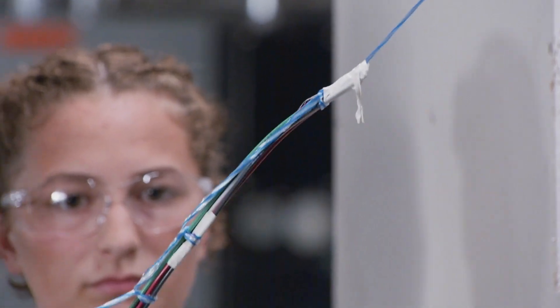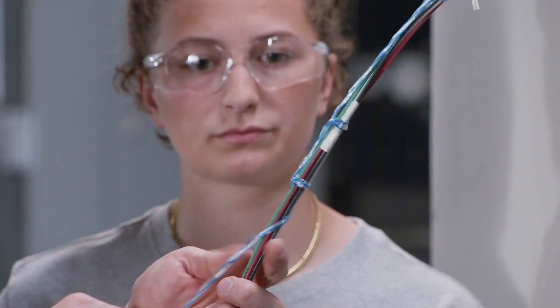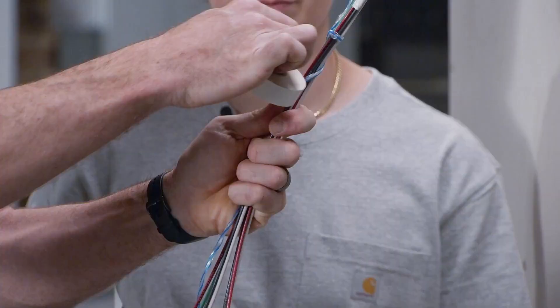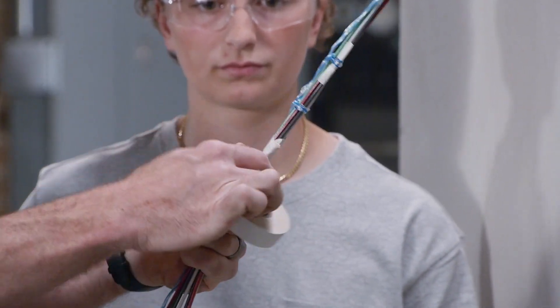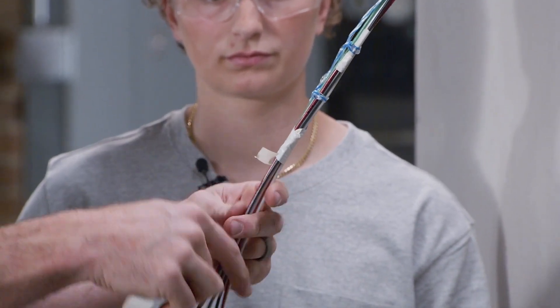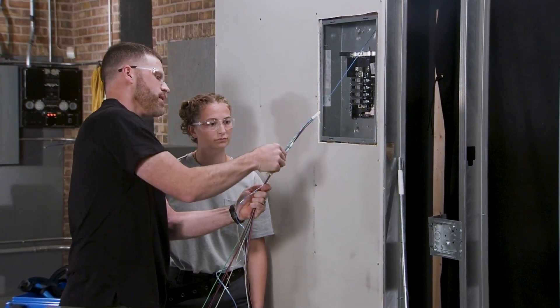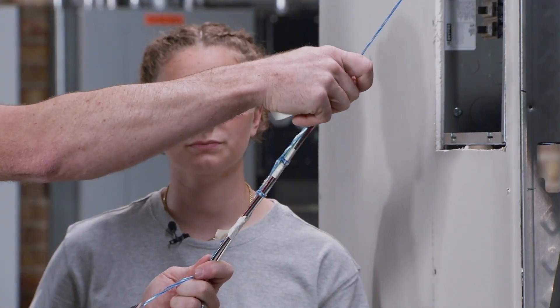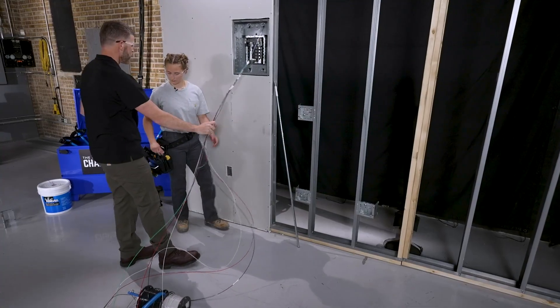Tape up the front of the head. I like to always leave a little tail so it's easy to come off at the end, because we're not wasting any wire doing it this way — all the insulation is still on these conductors. Every time I do a half-hitch, I like to do three half-hitch knots — it's just a loop right over itself. When I get to the end, behind the third half-hitch, a couple wraps of tape so that string can't slide up. When we pull on this string, the harder I pull on it, the tighter these knots are going to cinch down on themselves — so the harder I pull, the harder it grabs these wires.